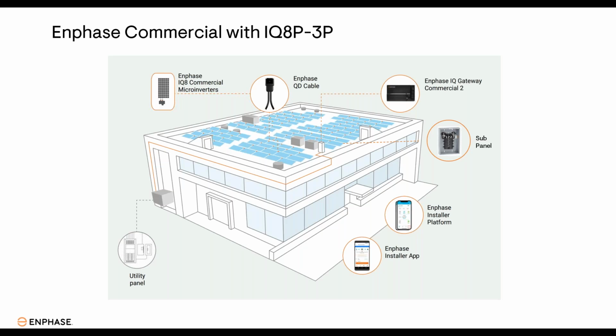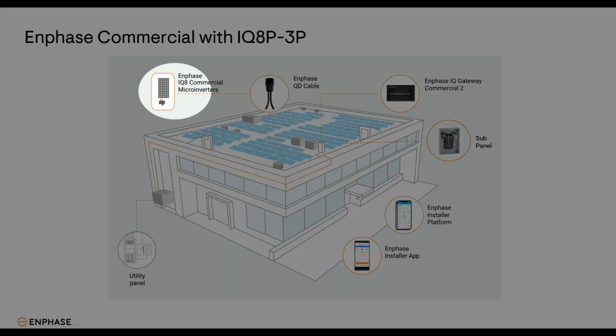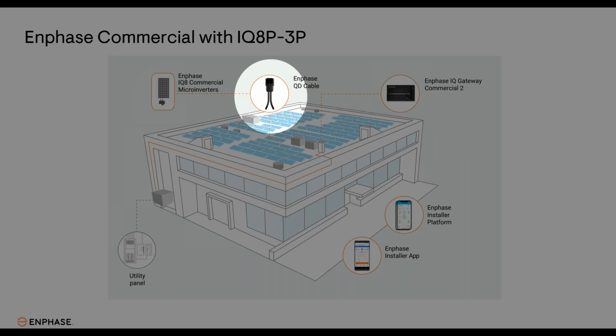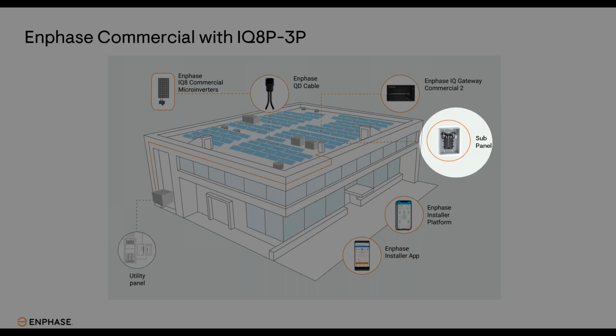You can see the overall items here, starting with the Enphase IQ8 commercial microinverter, then the Enphase QD cable, which takes the power over to a sub-panel board where each circuit lands on a 20 amp 3-pole breaker. Then it's combined in that panel and sent over to the utility panel for your point of interconnection.